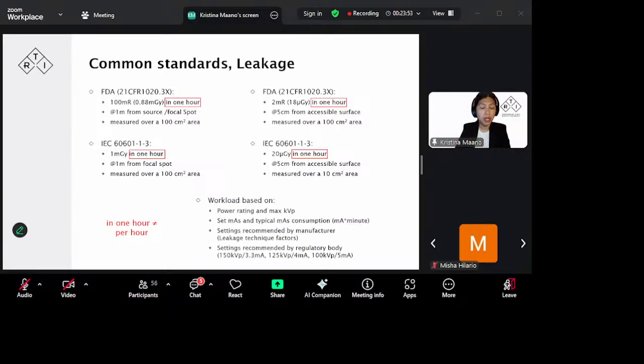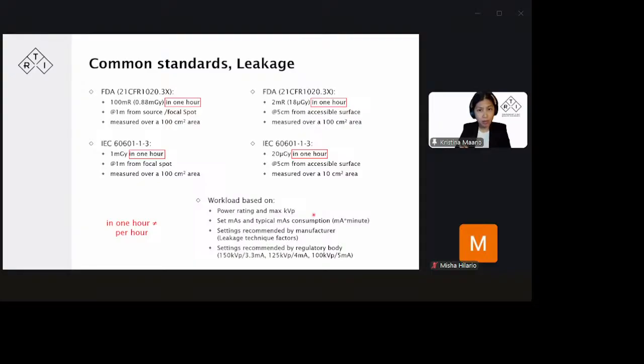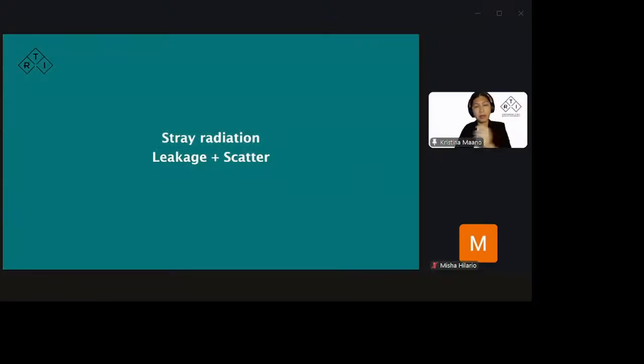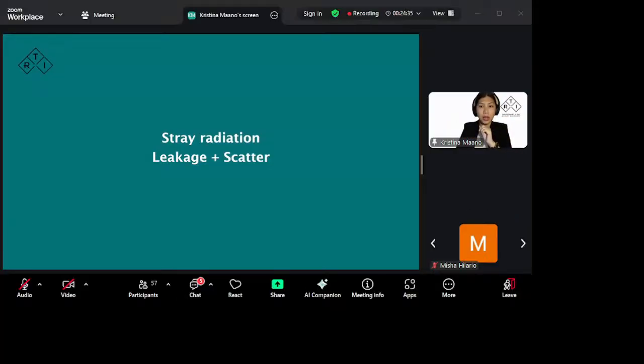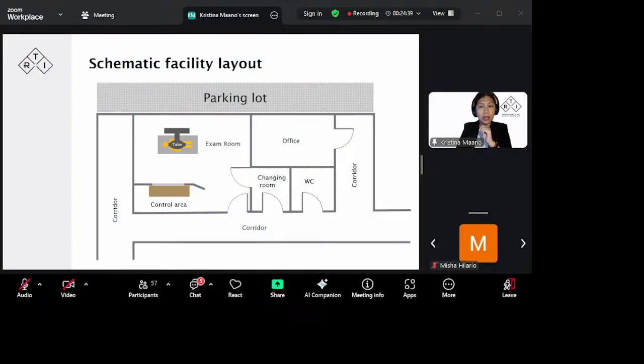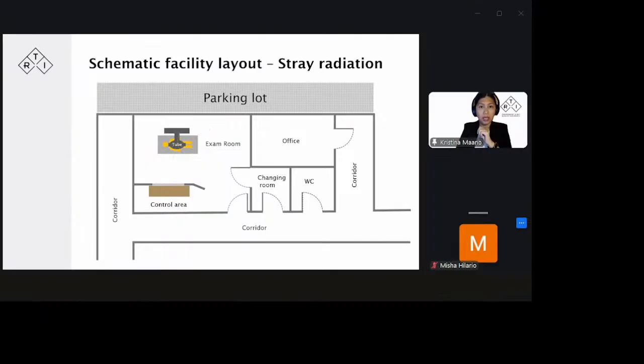So we do the workload calculation based on power rating and max kVp, set mAs and typical mAs consumption. And usually the settings are recommended by the manufacturer of the X-ray machine. However, if there's no recommendation from the manufacturer, you look into the requirements or the recommendations by your local regulatory body and use that when doing your tube leakage measurement and testing. All right, so going back to the topic, stray radiation is not just tube leakage, but also scatter. So we said that during a normal exposure, both the tube leakage and the scatter can be generated.